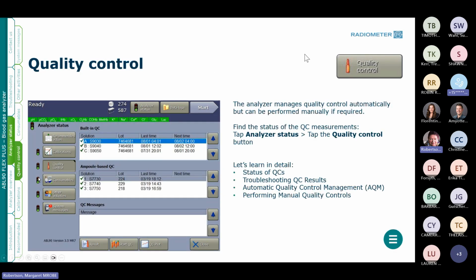So then, getting into quality control, the analyzer manages two types of quality control. One, of course, is the internal quality control, which is three levels, and these are in the top part of the screen, A, B, and C. It also has the capability of having external quality control as well, and they're handled a little bit differently than the internal ones. All of this and the calibration is all automatic on the analyzer.